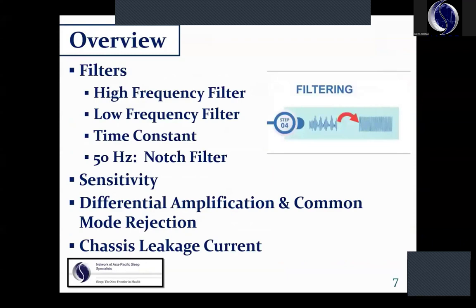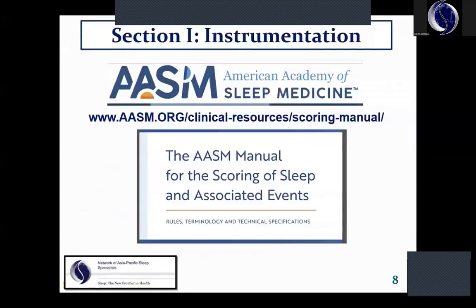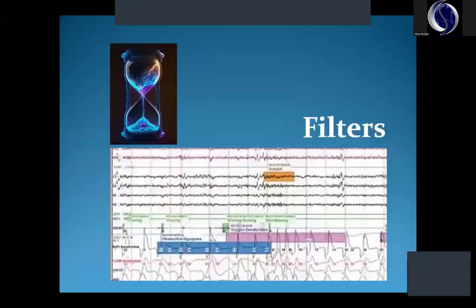We're going to start talking about filters, the high filter, the low filter, time constant, and the 50 Hertz notch filter. We'll talk about sensitivity. We'll also talk about differential amplification and common mode rejection and chassis leakage current. All of the values for filter settings are derived from the AASM manual for the scoring of sleep and associated events. That's the American Academy of Sleep Medicine.